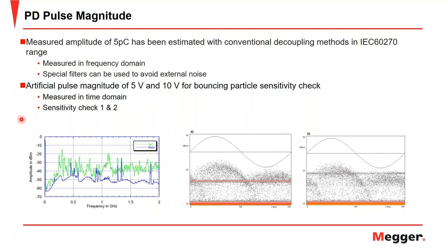So the sensitivity check has two steps. One is performed at the factory of the GIS manufacturer, where an artificial fault is created with a metallic spike or a hopping particle, whose size is chosen to give a 5 picocoulomb peak signal. And when doing this, they use the conventional decoupling methods of the IEC 60270 to be sure that they do indeed have this 5 picocoulomb peak signal and are able to get a PRPD pattern of this 5 picocoulomb signal.